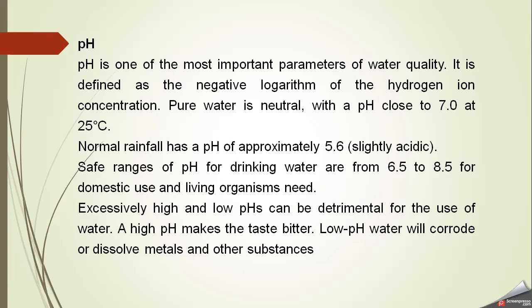One of the most important water quality parameters is pH, defined as the negative logarithm of hydrogen ion concentration. Pure water is neutral with a pH close to 7 at 25°C. Normal rainfall has a pH of approximately 5.6, which is slightly acidic. The safe range for drinking water is 6.5 to 8.5. Excessively high or low pH is detrimental for humans and distribution systems — high pH makes water taste bitter, while low pH causes corrosion and dissolves metals.